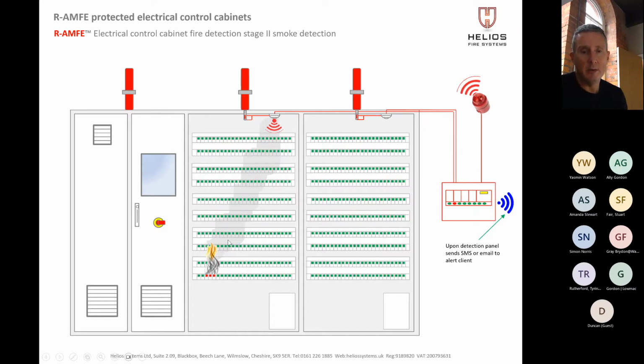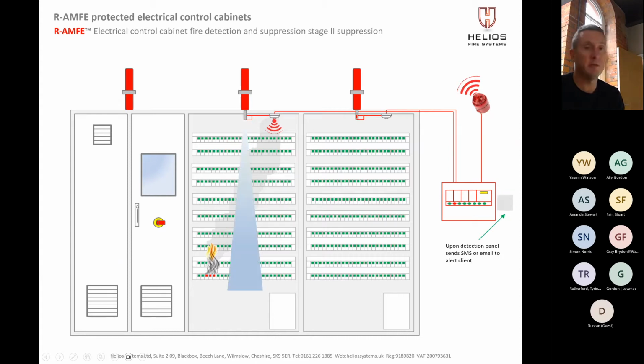So stage 2. What we're looking at here is normally the system is detecting all the time. Upon detection of a fire inside, and let's say it's worst case scenario at the bottom part of the cabinet, the smoke detector will alert. It automatically sends the signal through to the alarm, which then sends an SMS out to say there's obviously an issue, or to a monitoring station, sets the site alarms off. Here, so we have the SMS, and then we have site alarms, and then secondary, it then sends the signal off to the system to deluge.